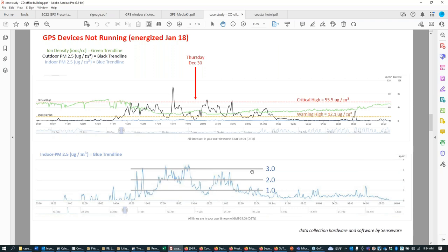Okay, so I want you to remember that. This is what happened inside when wildfire smoke was being introduced into the building with MERV 13 filters. And again, EPA says anything below 12 is considered healthy. So this showed my building owner, my client, that the MERV 13 filters did a good job mitigating this wildfire smoke and the particles that were being introduced into the building.